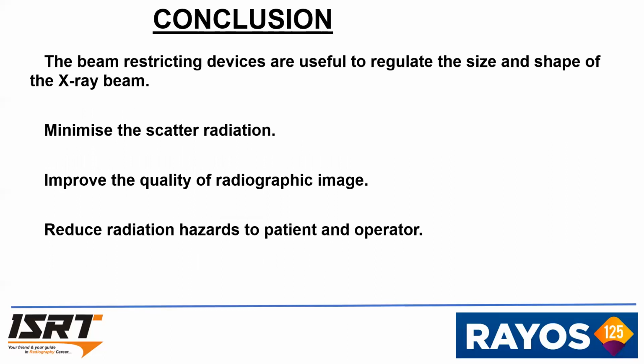My conclusion is that beam restricting devices are useful to regulate the size and shape of the X-ray beam, which definitely minimizes scatter radiation, improves the image quality of the radiograph, and reduces the radiation hazards to the patient as well as the operator.